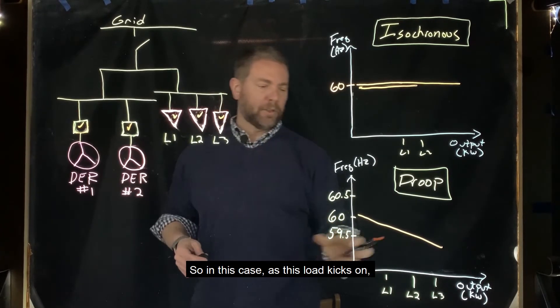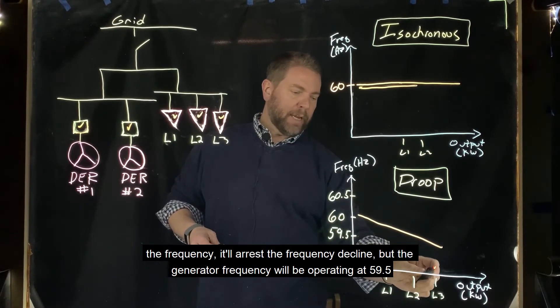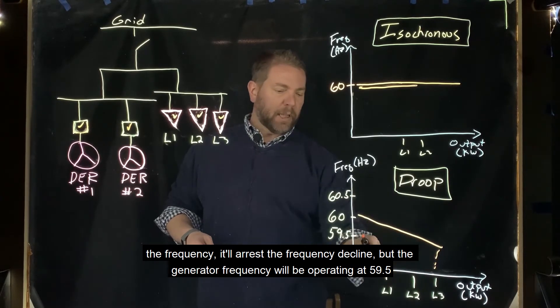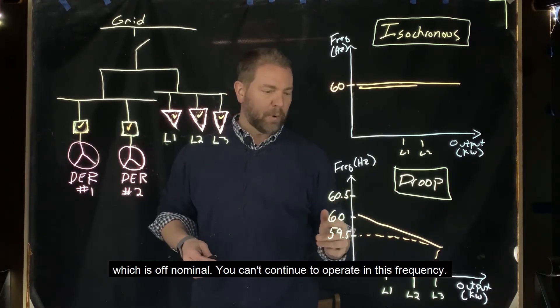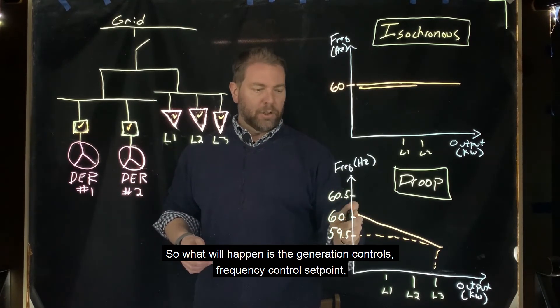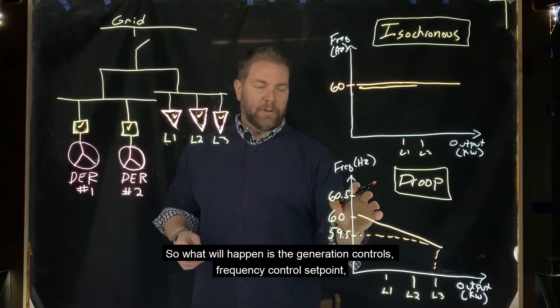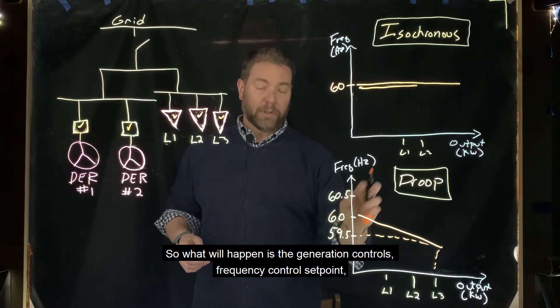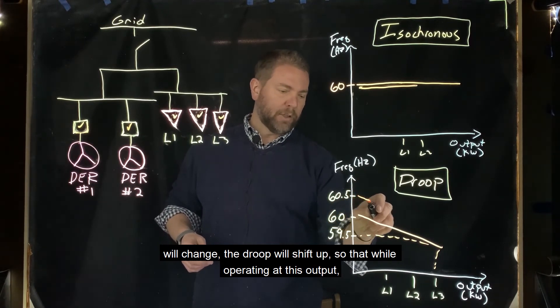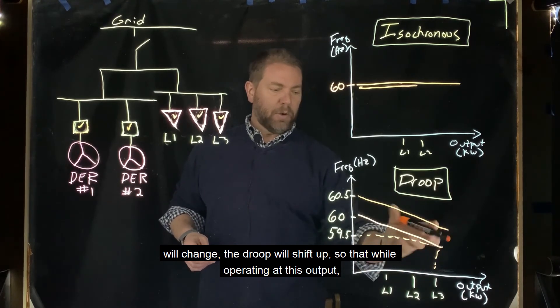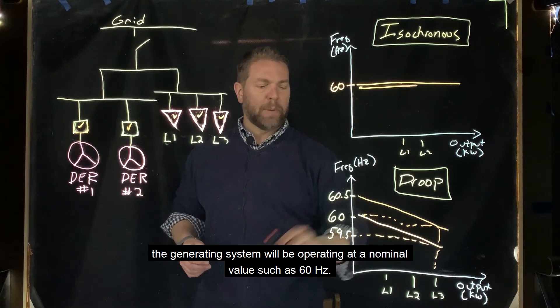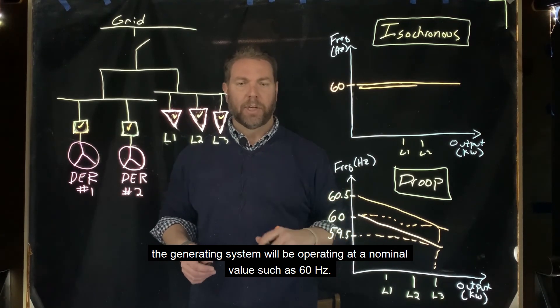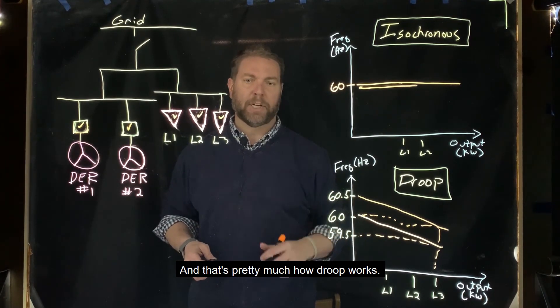As this load kicks on, the frequency will arrest the frequency decline, but the generator will be operating at 59.5 Hz, which is off nominal. You can't continue to operate at this frequency, so what will happen is the generation control frequency set point will change. The droop will shift up so that while operating at this output, the generating system will be operating at a nominal value such as 60 Hz. And that's pretty much how droop works.